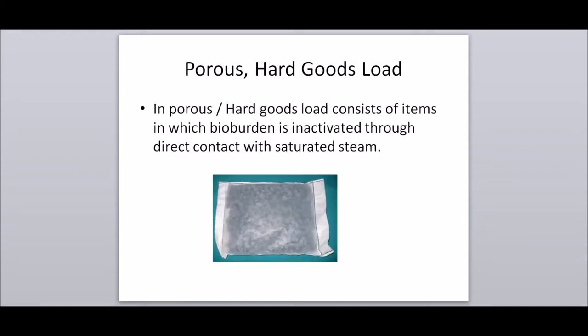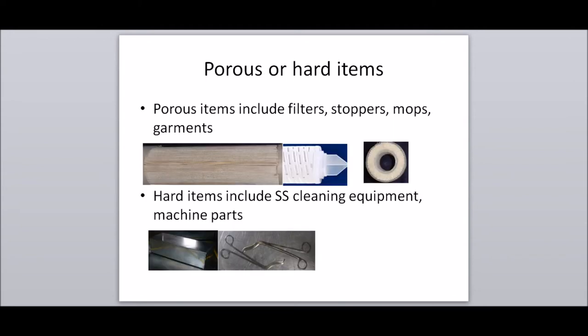Porous or hard goods load: loads consisting of items in which bioburden inactivation is achieved through direct contact with saturated steam. Porous items include filters, stoppers, gloves, and garments. Hard items include aseptic cleaning equipment and machine parts.